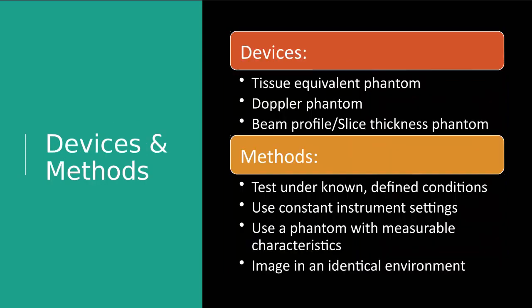There are particular devices and certain techniques that they are required to use when they come in to perform QA. The devices we commonly use with clinical ultrasound are a tissue equivalent phantom, a Doppler phantom, and a slice thickness phantom. Those are all going to test different components of the machine and the transducer. The methods are very particular.